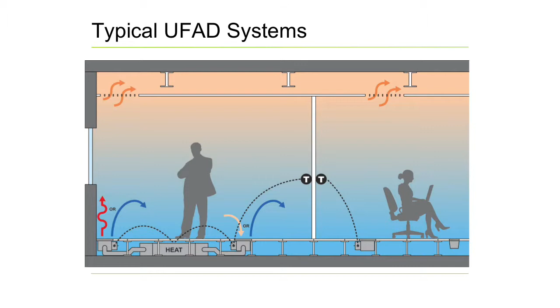This one is basically showing an underfloor fan box rated only for heat. It shows a perimeter system that uses ducted supply—could be fabric or sheet metal duct—to diffusers that, in cooling mode, just use cool plenum air. But if it goes to heat, if the thermostat on the wall calls for heat, these boxes will close off to that plenum air.